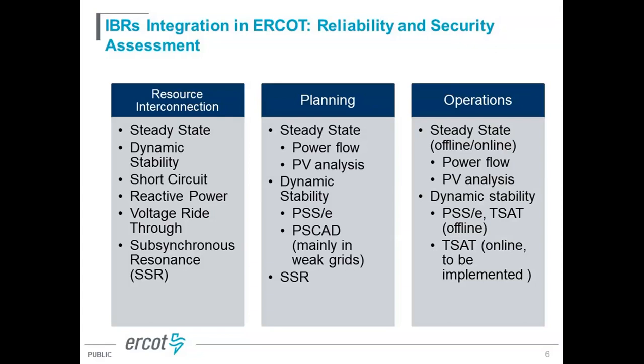Going to the planning stage, there is also a very typical analysis and assessment toolset. For the steady state and dynamics, something to highlight here, following what Ryan mentioned earlier, is that depending on the area, certain areas with a high concentration of inverter-based resources and a weaker grid have stability challenges that need to be identified or at least addressed. As a result, in ERCOT, we have started to consider and perform PSCAD studies, mainly for the weak areas we identify, to ensure the assessment can capture all potential control instabilities or oscillatory response due to system strength issues.